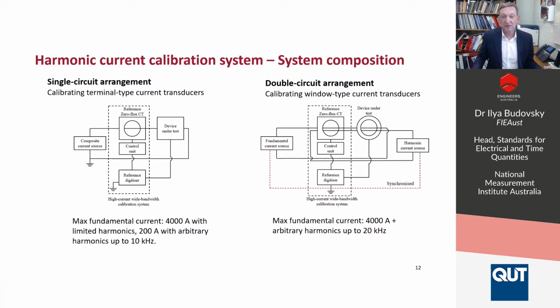Alternatively, we've introduced the double circuit arrangement, where there are two separate circuits going through the reference current transformer and the device under test. 50 hertz and a small number of its harmonics are generated in one circuit, and then the harmonic currents are added in the second circuit. And of course, the 50 hertz source and the harmonic source are synchronized. And then again, both devices are measured by the digitizer.